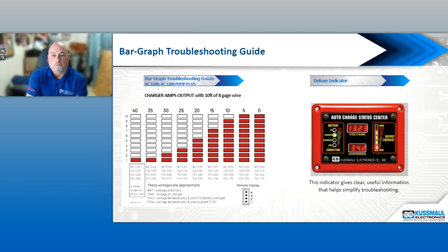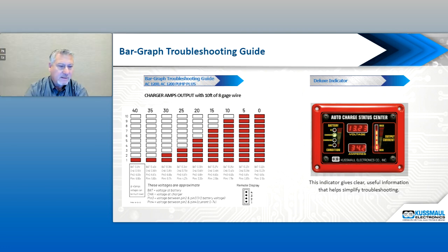Here's just a quick display, kind of the bar graph troubleshooting guide, just kind of explaining the charger amp output. It's showing 40, 35, 30, 25, 20. What that's showing is the amperage that the charger's putting out, and kind of just showing what it's going to do on the bar graph display. If you have 40 amps on a 40 amp charger, the current is flowing out, it's going to only illuminate one of the LEDs on the bar graph. If you only have 5 amps going out, it's going to show that it's full.